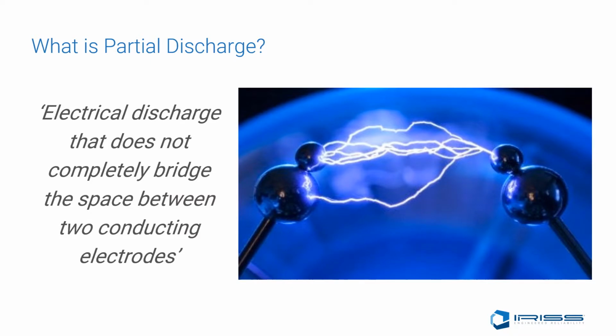So, what is a partial discharge, you may ask? Well, it's an electrical discharge that does not completely bridge the space between 2 conducting electrodes, and 80% of failures in switchgears are directly related to partial discharge events. These partial discharge events can be caused by gas-filled voids in solid insulation, which are bubbles in the jacketing of the cable, which can lead to failure over time. These voids can be caused by substandard cabling manufacturing practices or environmental exposure.